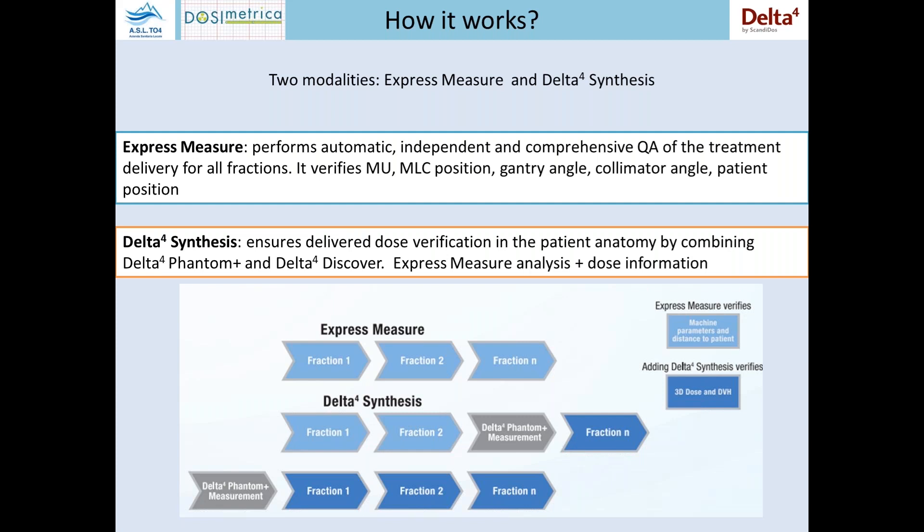It is possible to check the monitor units, the MLC position, the gantry angle, the collimator angle, and the patient setup. But together with the Delta4 Phantom, it can work in Delta4 Synthesis mode.